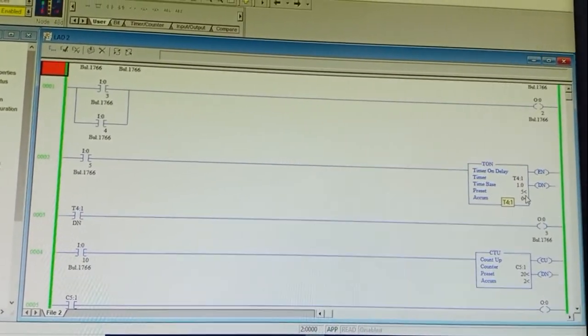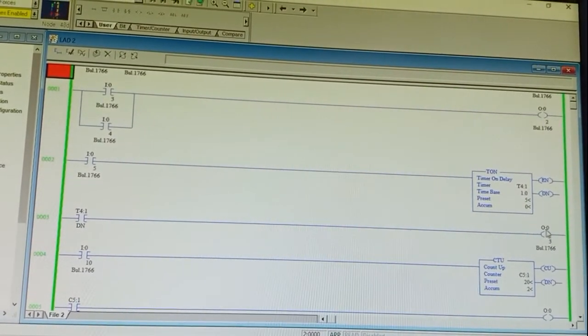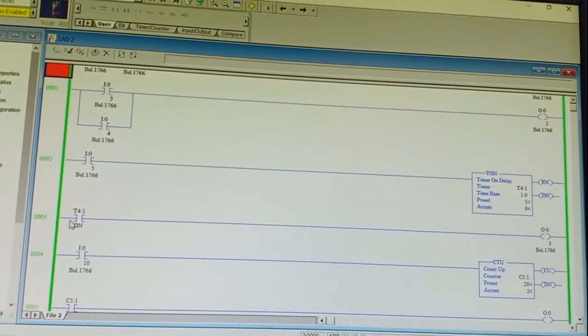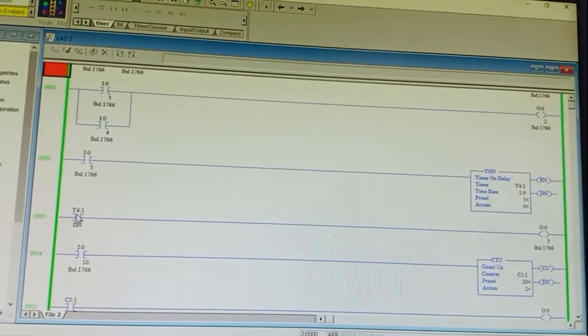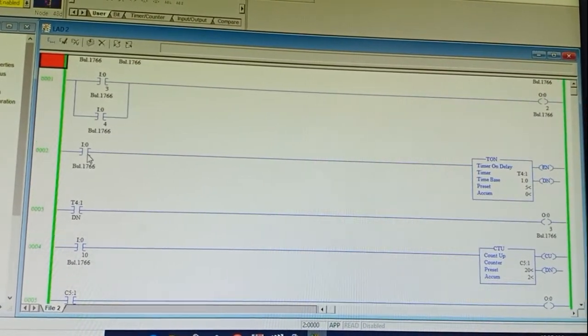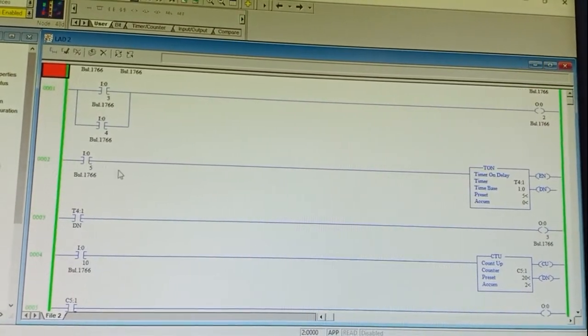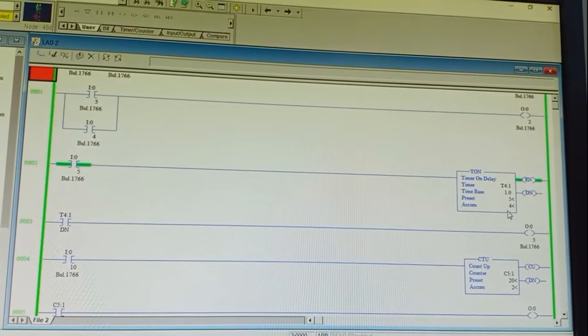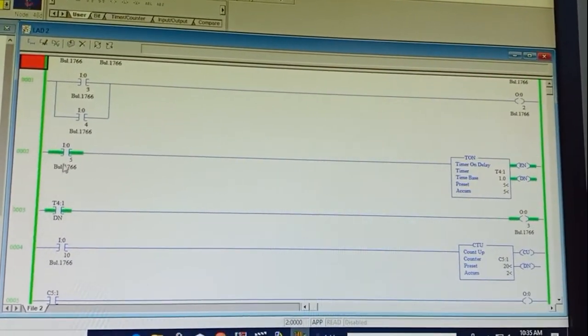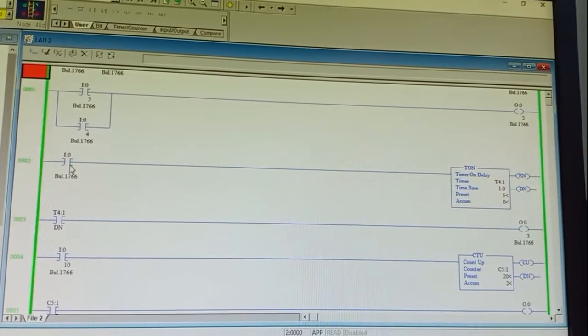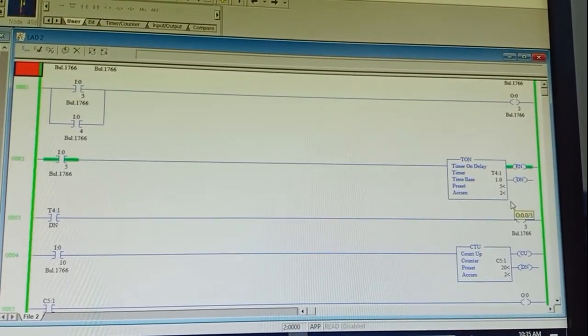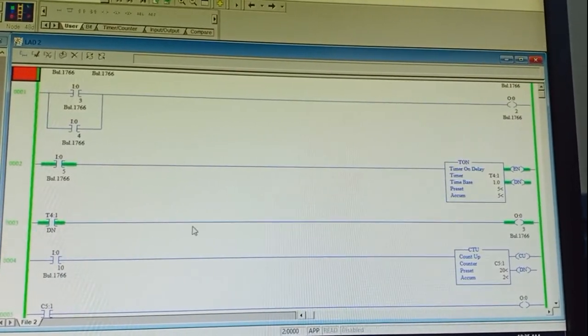Now the timer on-delay: preset value is 5 seconds, so after 5 seconds the bit will turn on. The output switch will turn on, and the done bit indication uses the timer name slash DN. Rahul will turn on I5 — as soon as it turns on, the accumulator calculates. When it becomes 5, output turns on. When we toggle this bit to zero, the timer turns off. Turn it on again — accumulator counts and when both values match, bit turns on. This is timer on-delay.